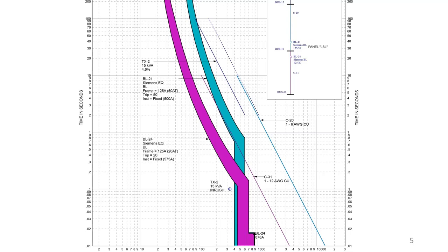In some cases, you may have to educate your customer about these things. They don't like it, but that's what we come across in many cases. So this is an example where it's a little tiny job, but it has to have selective coordination, and I replaced it with a fuse upstream. So if there's a fault in the 20 amp branch circuit, that 20 amp breaker will trip, but not tripping or clearing the upstream fuse.